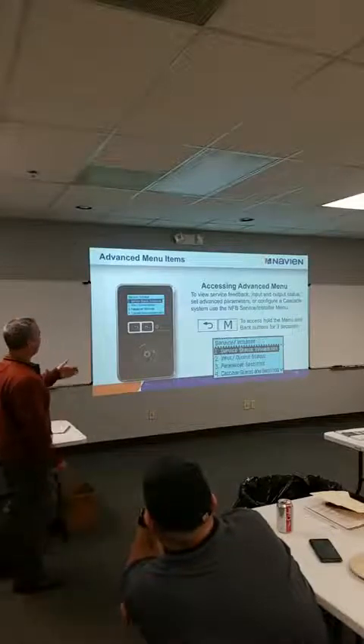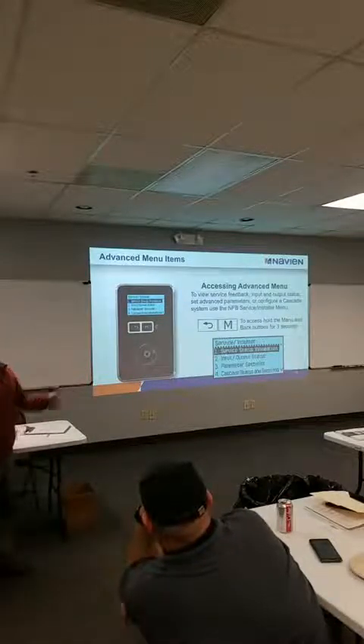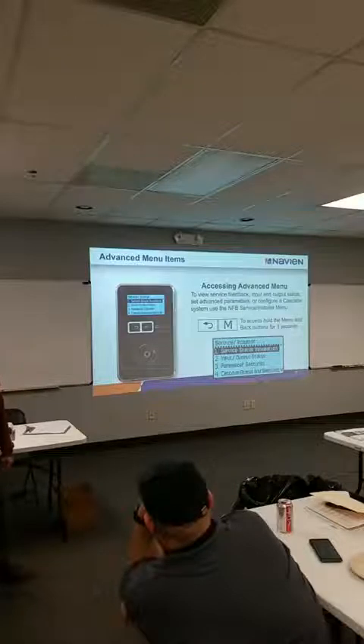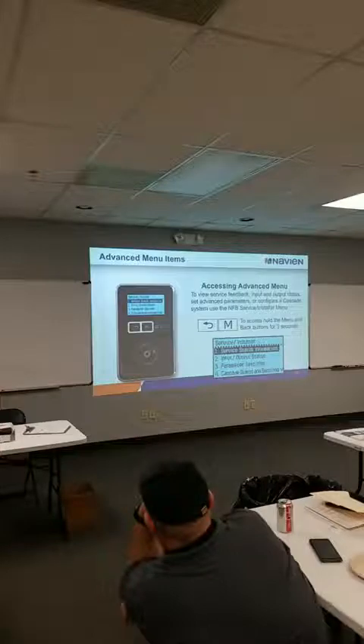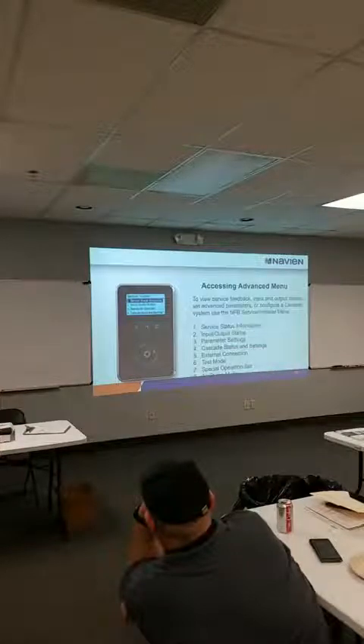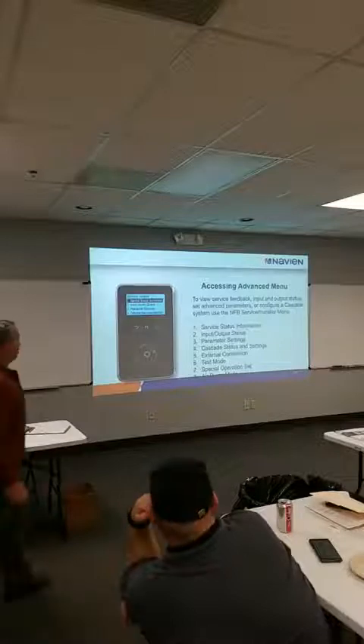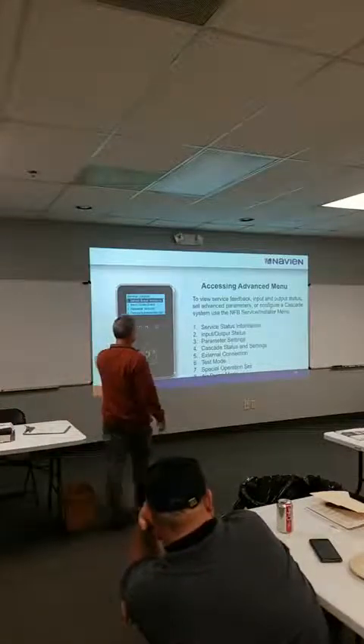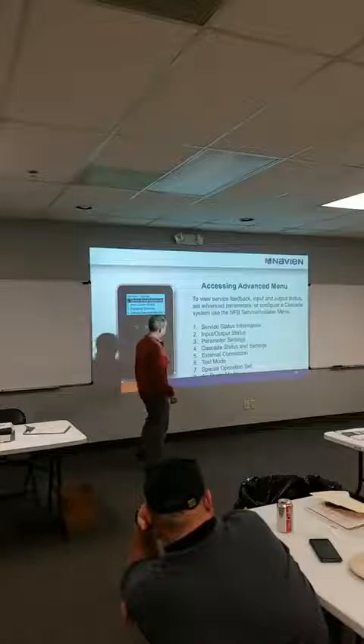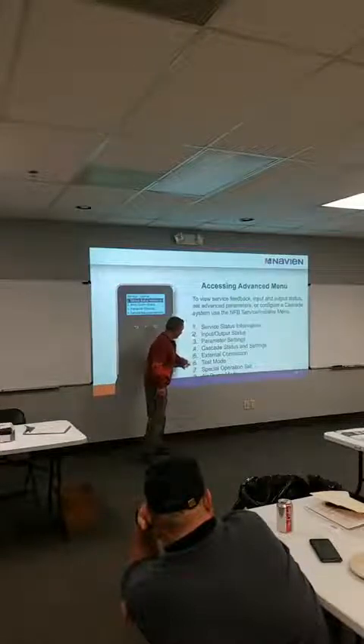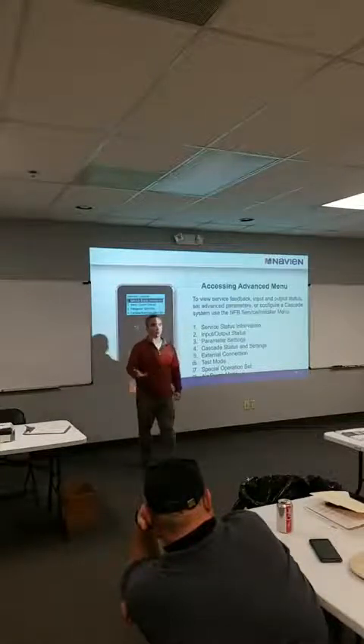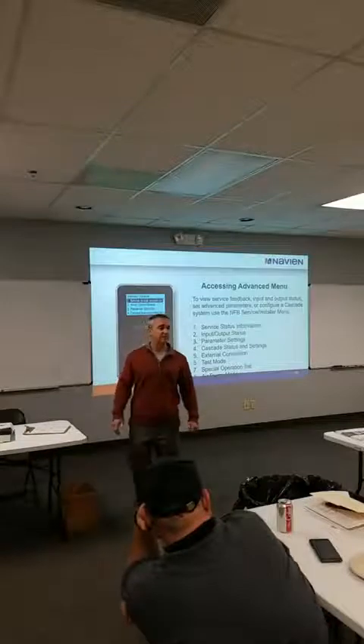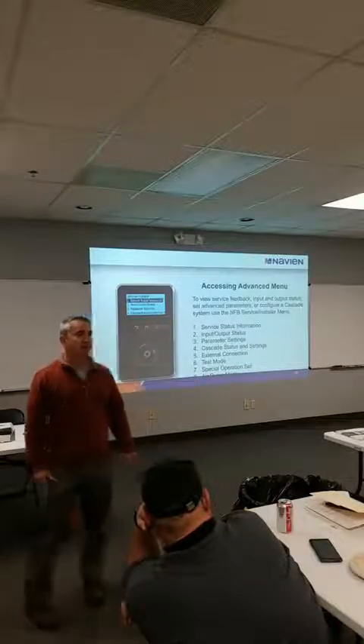So it's very simple to get to. It's all in English. You can dial through it. You don't even need a book to do it. And that's basically all eight settings; you can't really see that bottom one. So it gives you status and checks what you have. We can go in and test all the equipment. We can also force air purge mode to make sure all the air is out of the system, if you think you've got air gathered in that heat exchanger.